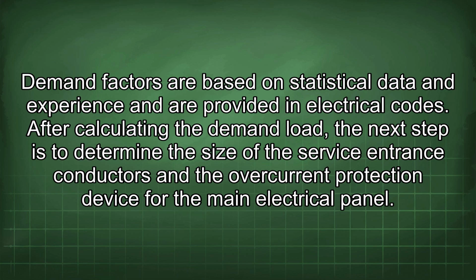Demand factors are based on statistical data and experience and are provided in electrical codes. After calculating the demand load, the next step is to determine the size of the service entrance conductors and the overcurrent protection device for the main electrical panel.